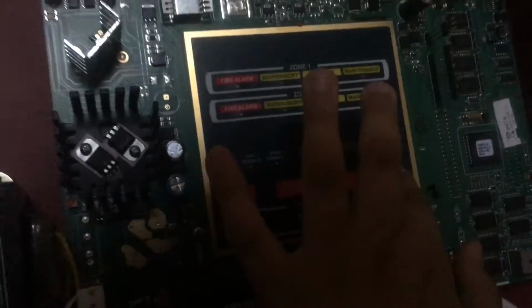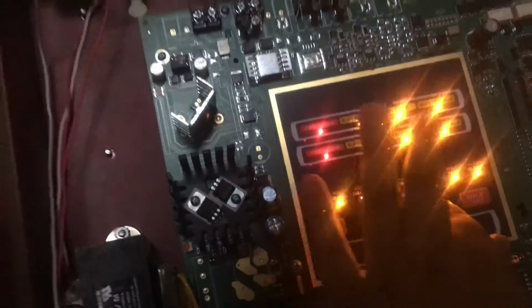Walk test, you hold that down for like 5 seconds. And then when you pull the pull station, it only activates for a few seconds so that you don't have the alarm constantly blaring. Then you just reset to stop that, and test your zones. Then down here, of course, we have our batteries. If I unplug this, now we have a power trouble because it needs batteries to operate properly.